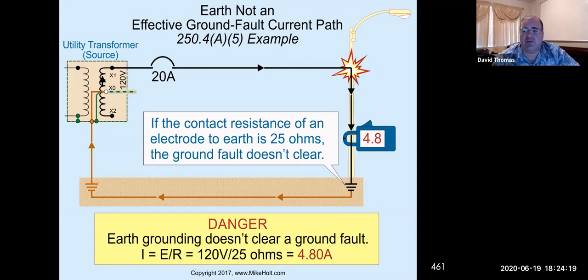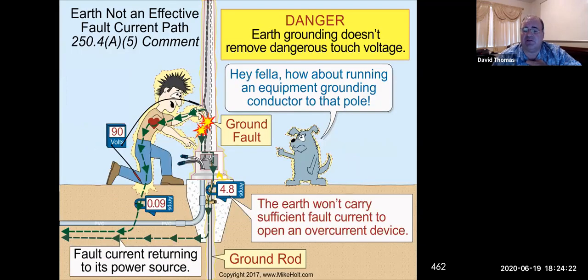So under ground fault scenarios, we do trip the breaker. Earth is not an effective ground path. Now, this is actually more of the scenario I was talking about, that little girl getting killed. They did bring a hot and a neutral in here, but they just did not ground the system properly. They're showing a ground rod in here, but they didn't put any equipment ground in the PVC pipe. So this is exactly, in essence, what happened with that little girl. Any electrician should know why we ground and how we ground, and what we avoid. This is a situation we're trying to avoid by properly grounding things.